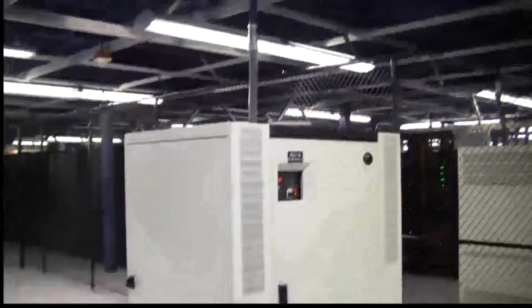We provide redundant circuits to each customer cabinet. So say one of your customers wants to come in here, we provide him an A circuit and a B circuit. The A circuit would come from like this one, the B circuit would come from like PDU 6. Each of these PDUs is set up onto two different UPSs. One goes to UPS 1, one goes to UPS 2.